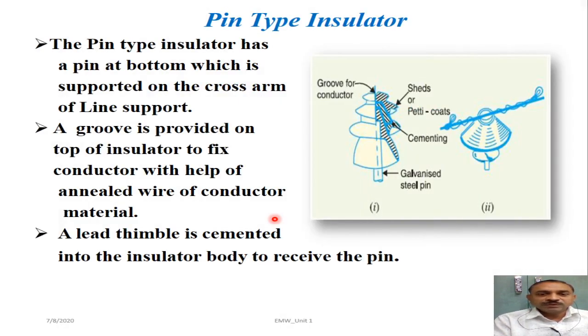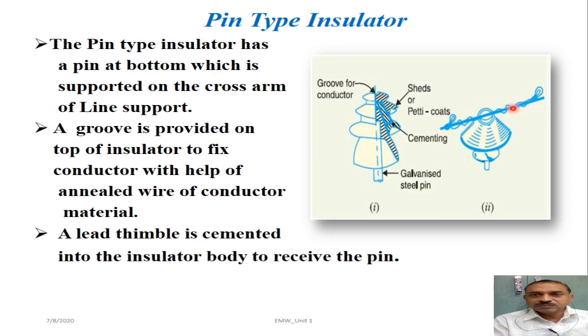Before we discuss the failure of insulator in detail, let us know the construction of the pin type insulator. The pin type insulator consists of a pin fitted at the bottom, made from galvanized steel, inserted inside the insulator with the help of a lead thimble cemented into the insulator body. At the top there is a groove where the conductor is fixed with annealed wires of the same material as the conductor. The insulator pin is fixed on the cross arm of the line support.